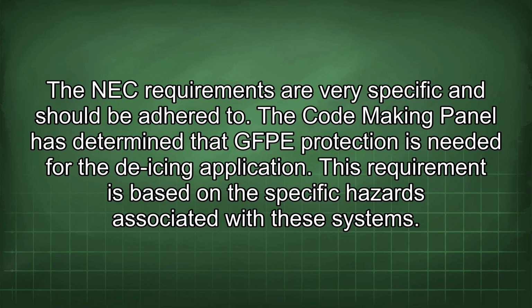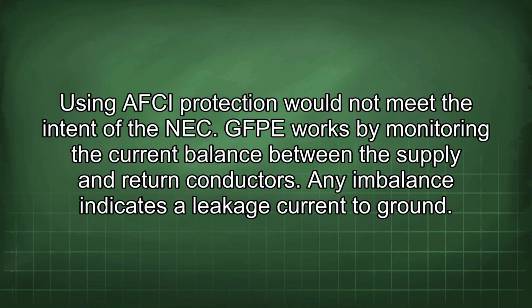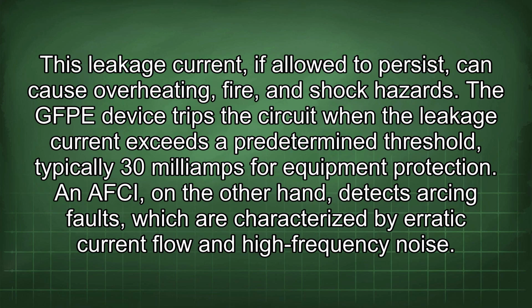The code-making panel has determined that GFPE protection is needed for the de-icing application. This requirement is based on the specific hazards associated with these systems. Using AFCI protection would not meet the intent of the NEC. GFPE works by monitoring the current balance between the supply and return conductors. Any imbalance indicates a leakage current to ground. This leakage current, if allowed to persist, can cause overheating, fire, and shock hazards.